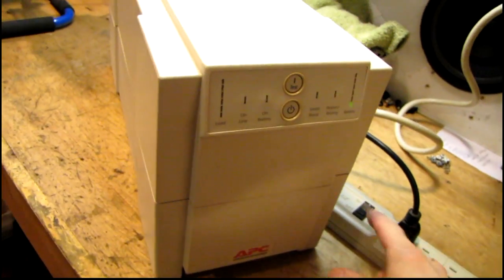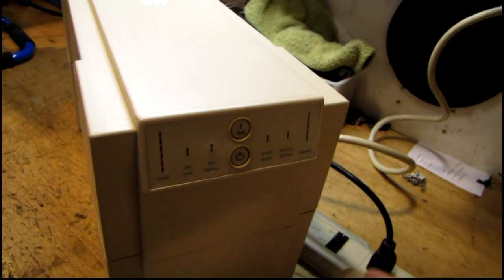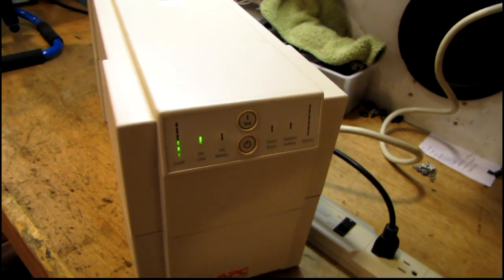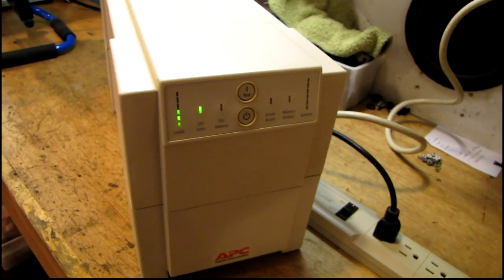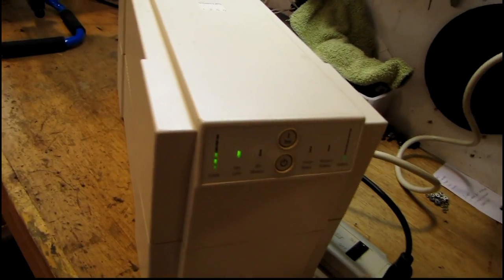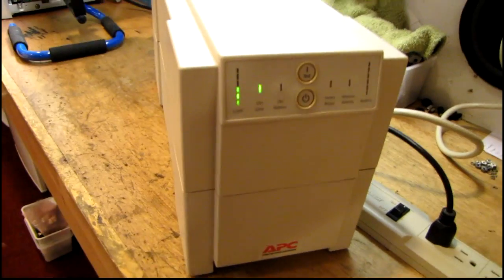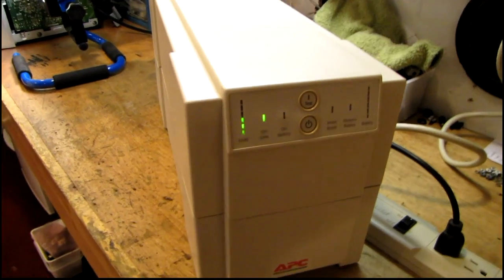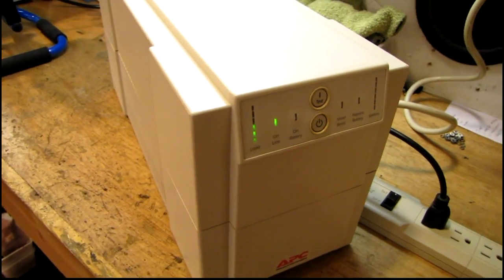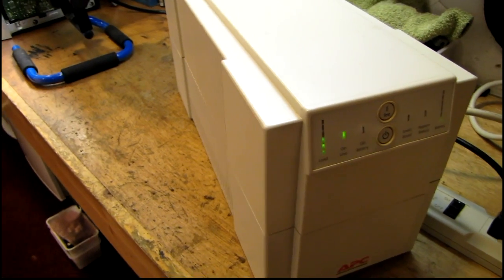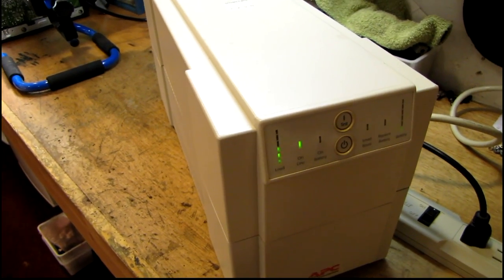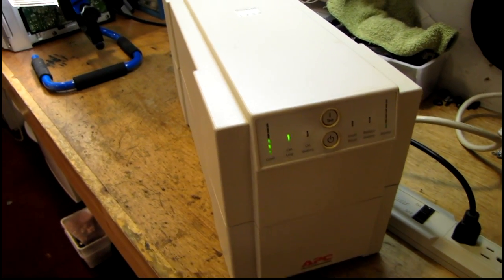So at this point, I'm going to turn the power back on. And disconnect the load, let it charge back up. Another thing I almost forgot to mention was, when you're replacing the battery packs in these, it's easier to find the replacements if you know the APC part number. In this case, for this unit, it's an RBC7.